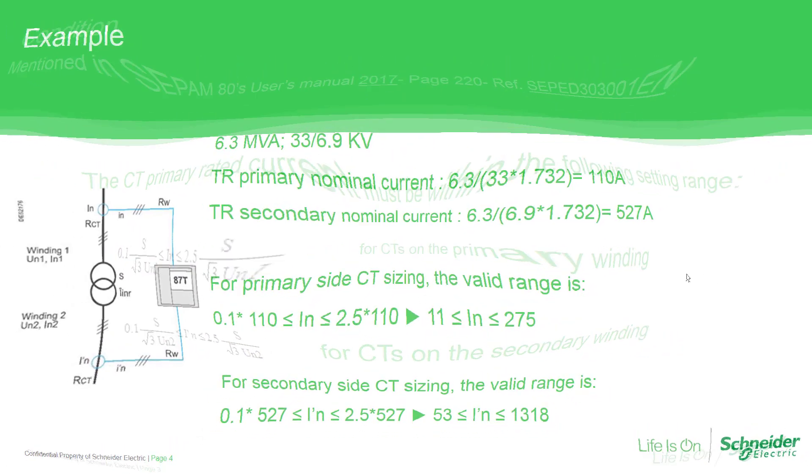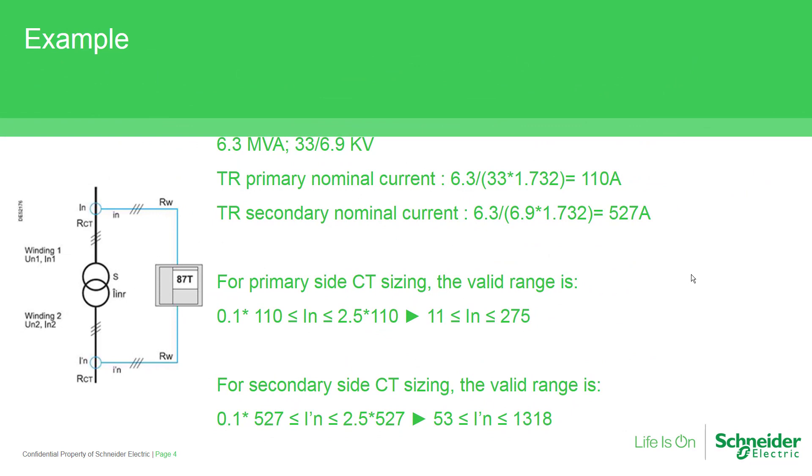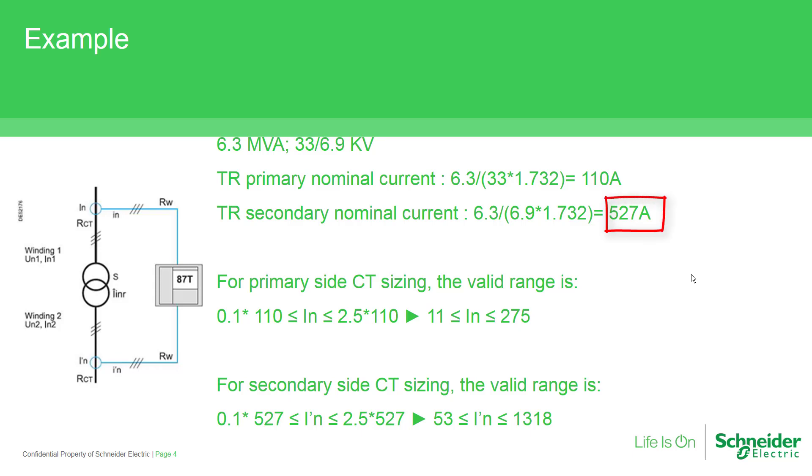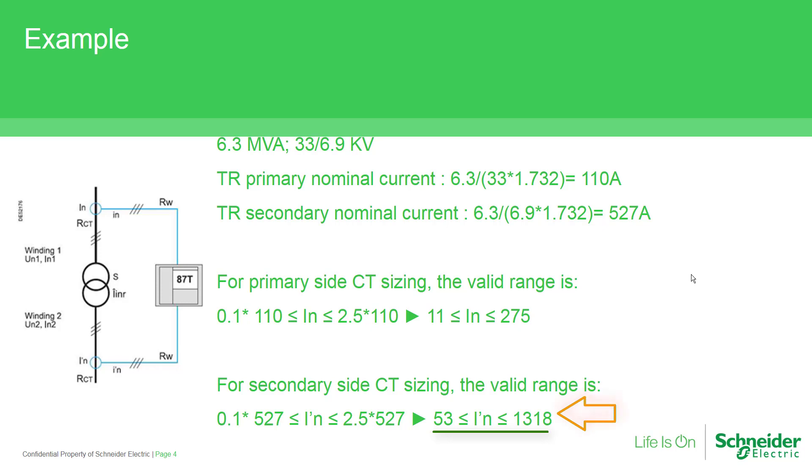As an illustration for a power transformer of 33 to 6.9 kilovolt and 6.3 megavolt ampere, primary winding base current is 110 amp and secondary winding base current is 527 amp. So the CTs located in primary winding should be sized in range of 11 to 275, and CTs located in secondary winding should be sized in range of 53 to 1318.